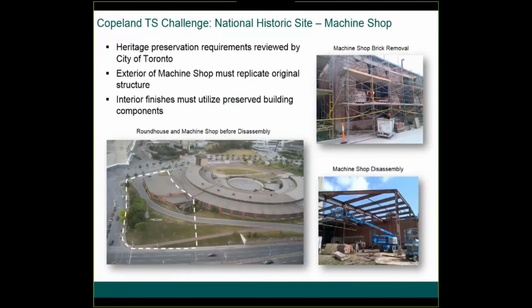We also determined that we had to place the transformer station underground in order to get the square footage required - approximately 50,000 square feet for transformers with medium voltage and high voltage switchgear - which meant we had to remove the machine shop. The heritage requirement was that we not only had to remove it carefully, we had to put it back, and it had to be identical or as close to identical as possible to the structure we removed.